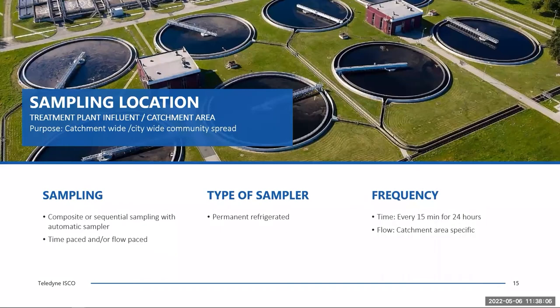The frequency for time-paced sampling will typically be at a 15-minute rate for 24 hours. For flow-paced sampling, the program is developed based upon the expected range of flows at that given location. My typical approach is to devise the program such that on an average flow day, the bottle is 80% full. That will guarantee that on a below-average flow day there is still an adequate amount of sample to deliver to the lab. And if I have an above-average flow day, I have some headspace in the bottle to collect more samples.